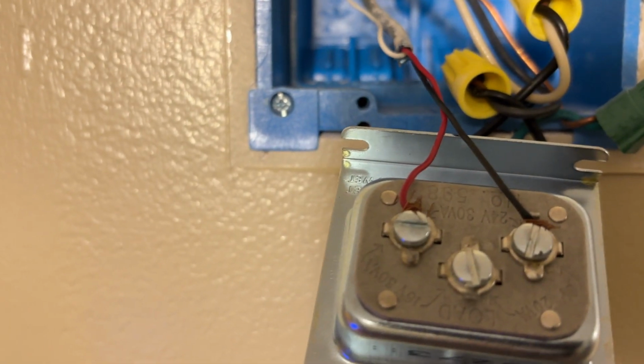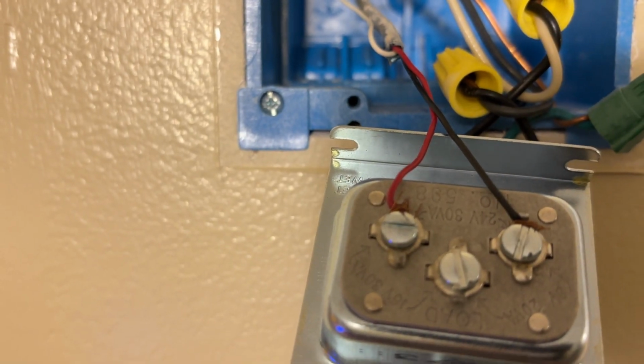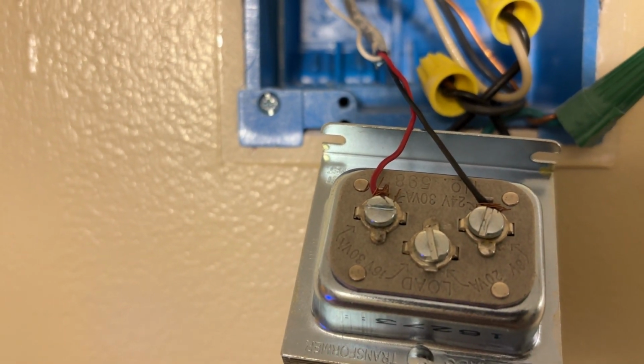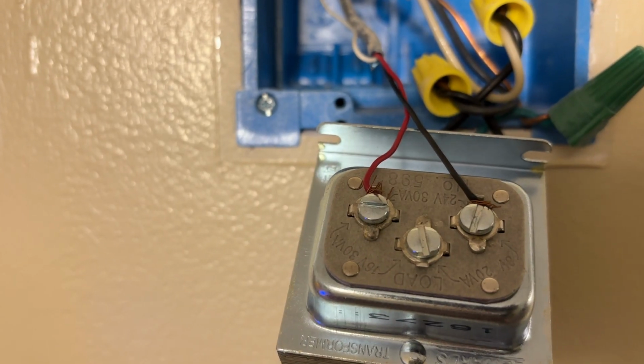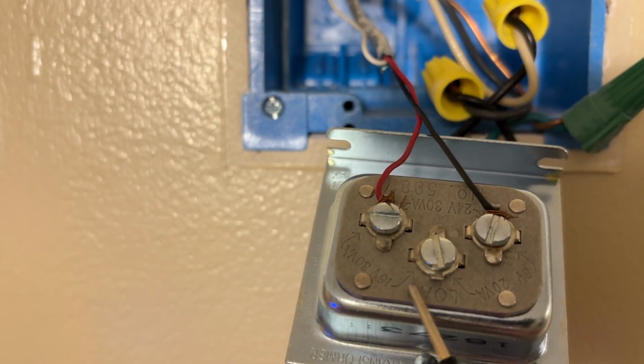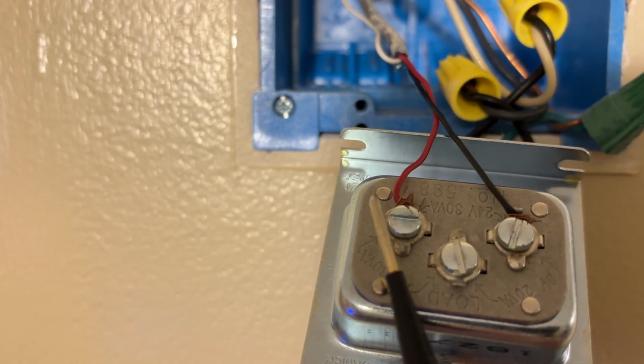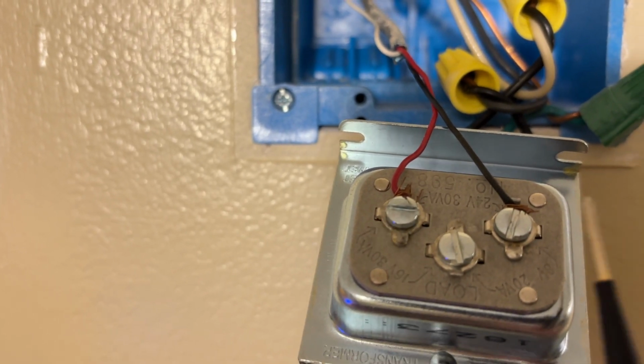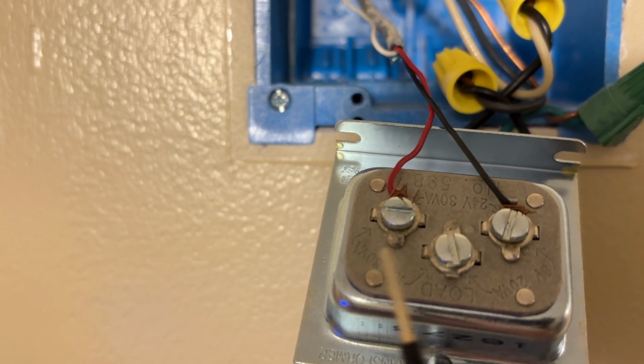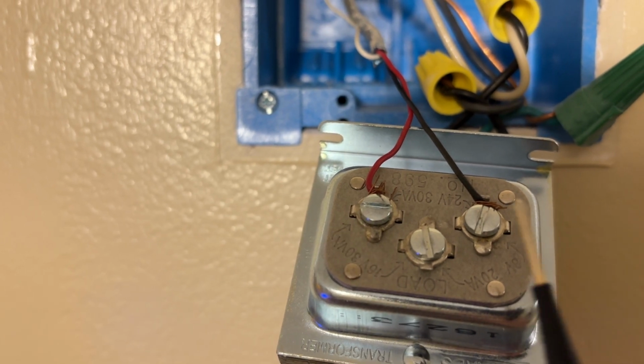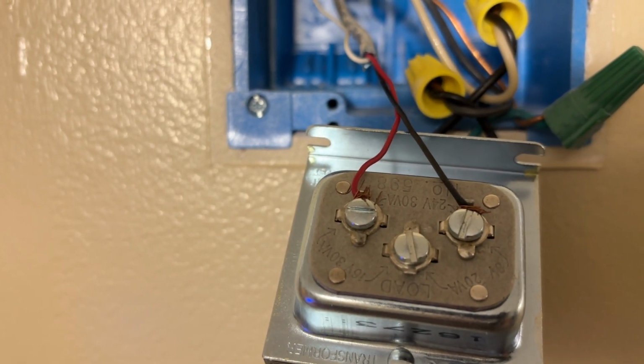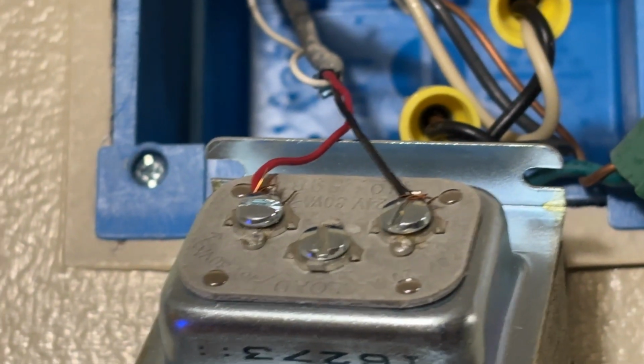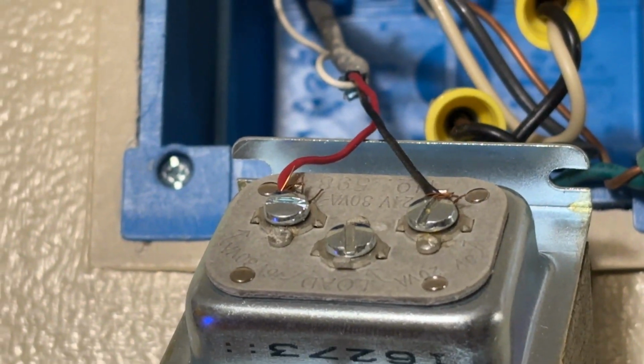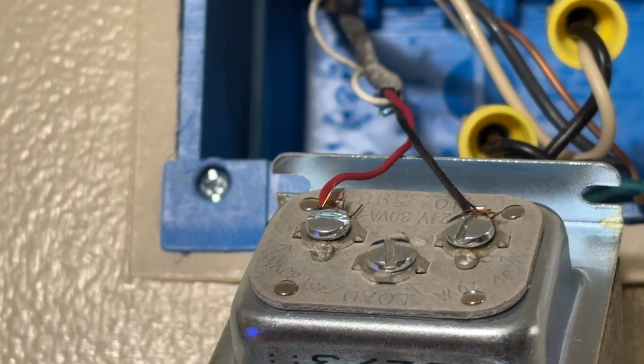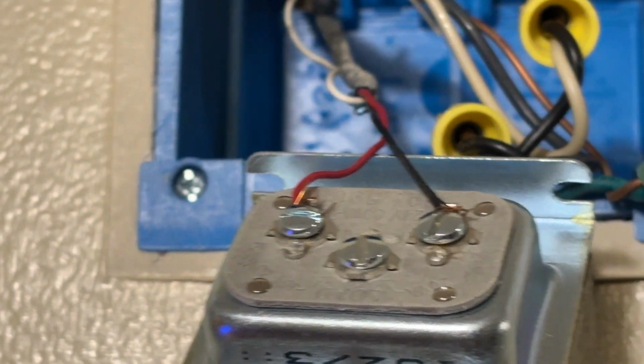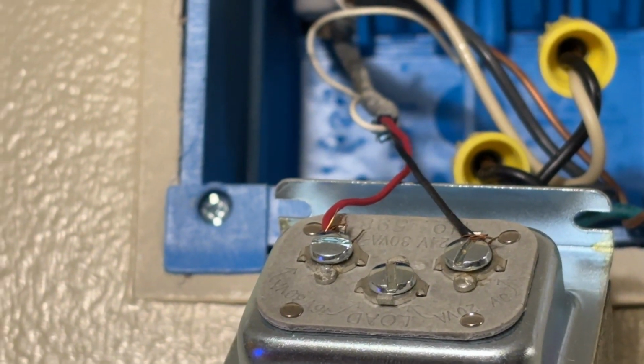This is a universal transformer that goes from 16 to 30 volts. Wiring it to here would be 16 volts, and we have it wired to 30, so we know that we are looking for around 30 volts of power between these two low voltage lines. Using our multimeter still set to VAC, we will test between the red and the black low voltage line. We were looking for around 30 volts.